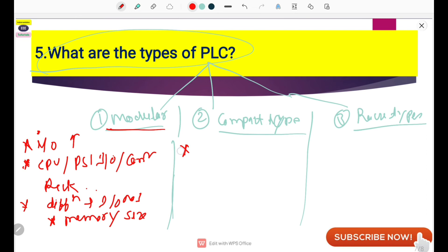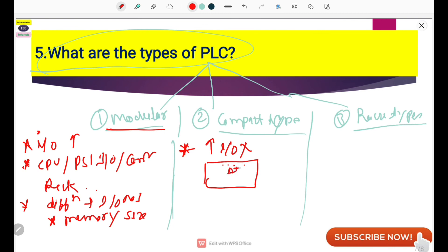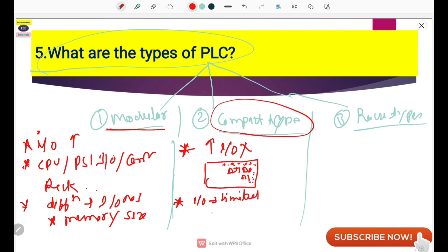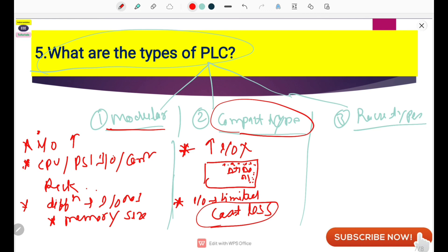In a compact type PLC, you don't have any possibility to increase the I/Os, because it is a simple PLC which comes with fixed DI, DO, and AI, and some communication connections are also provided. You cannot add external I/O cards or increase the I/Os. Compact type PLCs are used when installing a PLC on a single type of project where the I/Os are limited and fewer in number. The cost of the compact type PLC is also very low, making it suitable for package systems.